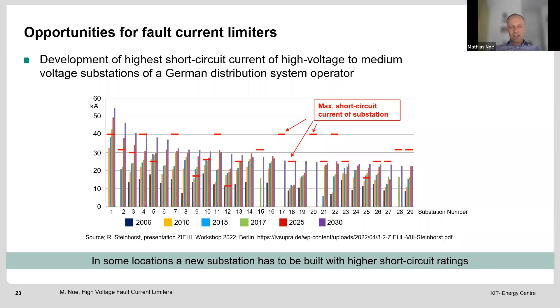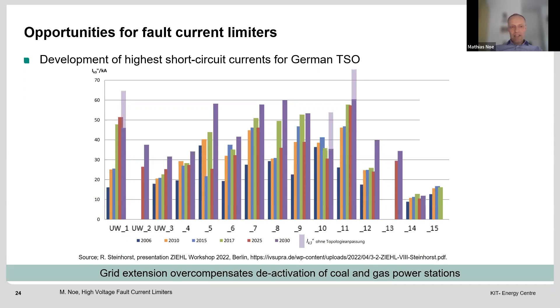This is also true for the transmission system operators in Germany. And you know, 63 kiloamps is quite a limit for circuit breakers, and in more and more places you come very close to that limit. And you see also the very fast rise in the short circuit current. So you have to do something, and of course you would think that the deactivation of coal and gas power stations would reduce short circuit currents. But as you see on the next slide, there is quite a big extension of the grid, not only in Germany.